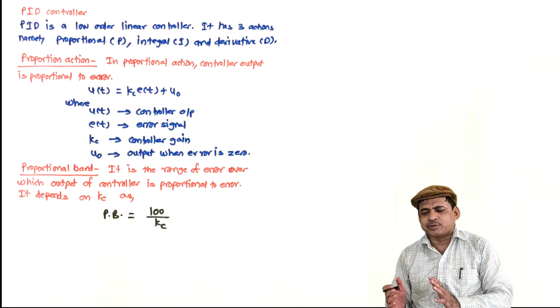So if you increase the controller gain, proportional band will decrease, and that characteristic can be represented typically like this. You can see here, the y-axis is controller output, the x-axis is error signal. When the controller gain is higher, the proportional band, this band of error, is smaller, because Kc1 is higher than Kc2. And for the smaller gain, this band increases. Why? Because PB into Kc is 100. And here, U0 is considered as 50% in this particular example.